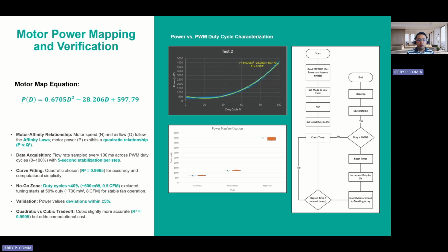By using this mapping, we can estimate the fan's power consumption without needing additional sensors, which is the key to the sensorless predictive tuning method. While I did explore using a cubic model, which showed a slightly better R-squared value but would require complex calculations and a larger dataset, the quadratic model was preferred for its balance between accuracy and computational efficiency.